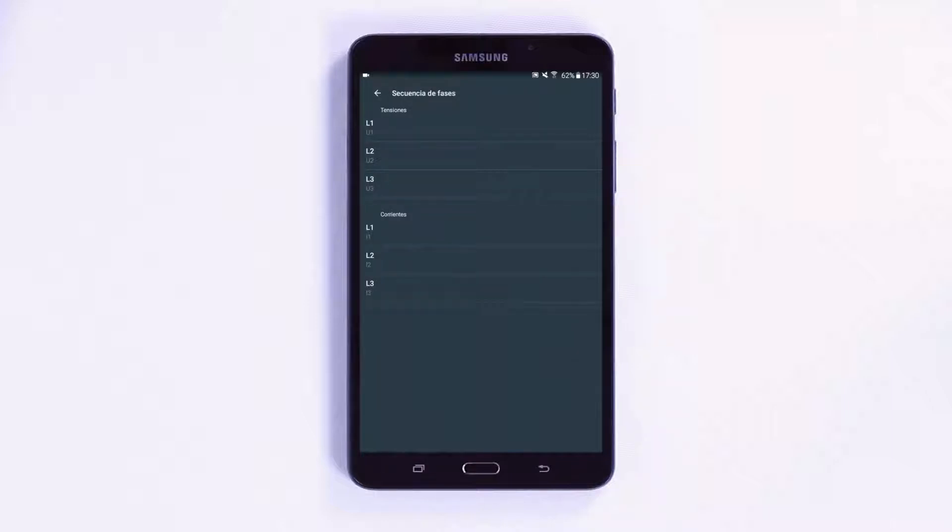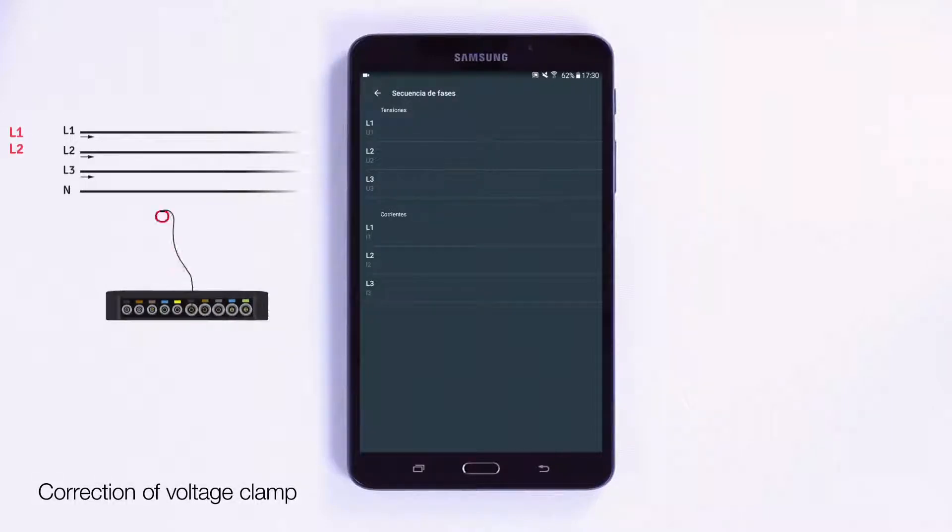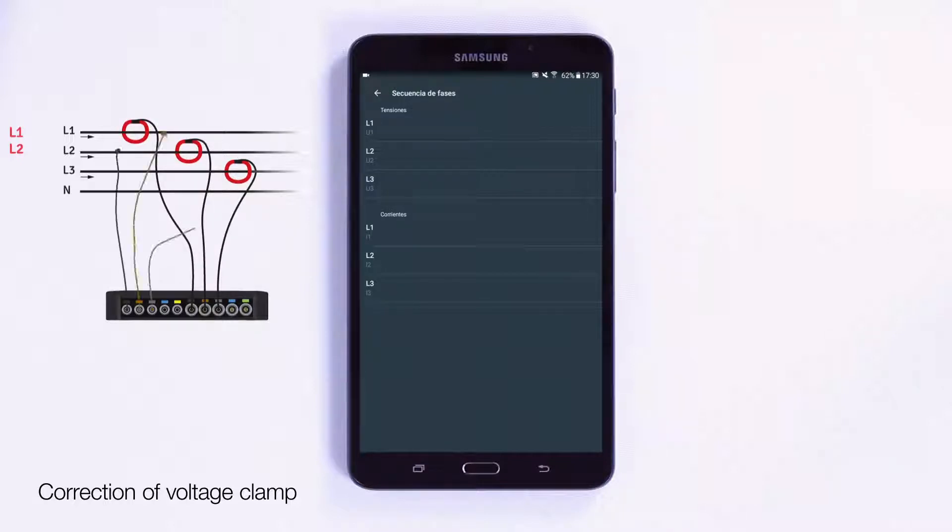The following example shows incorrectly connected voltage cables with the phase from line 1 crossing with the phase from line 2 and vice versa. This will generate an error in the reading of parameters such as the power factor, cosine phi, power and energy.